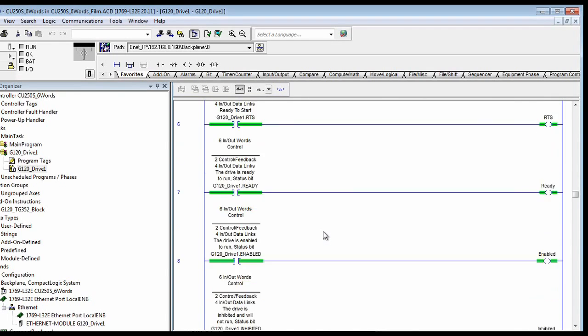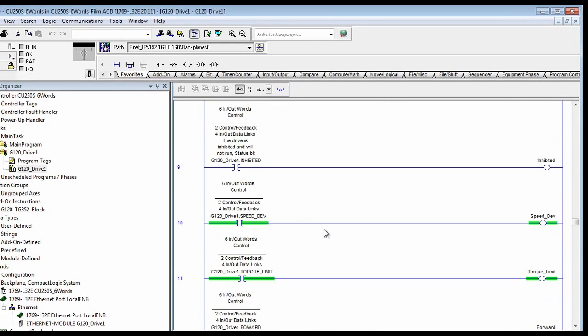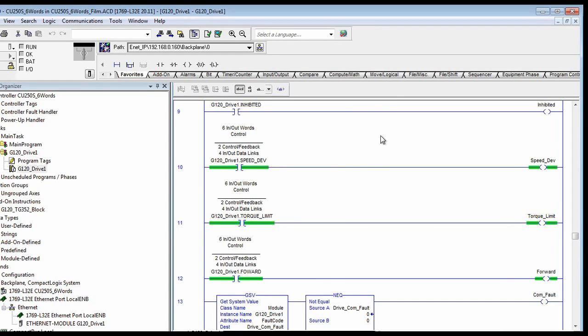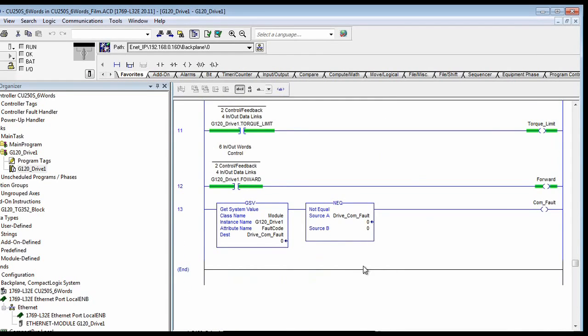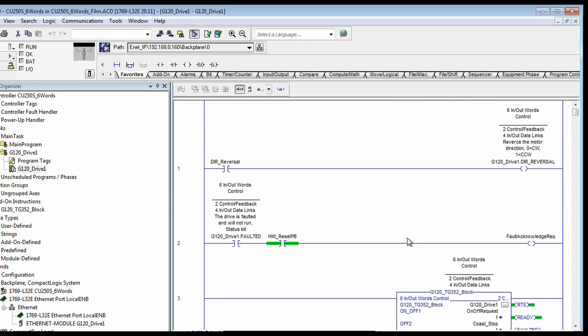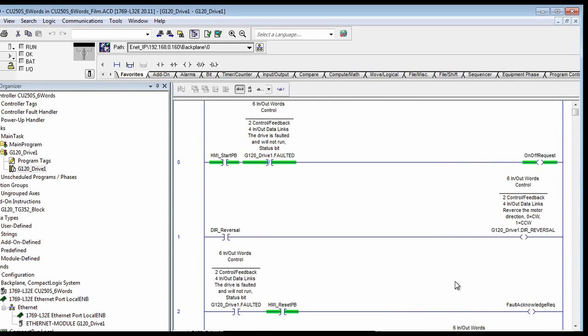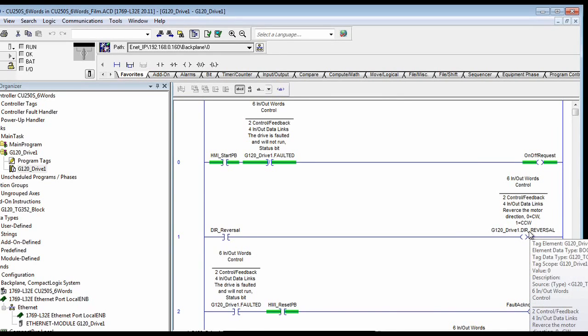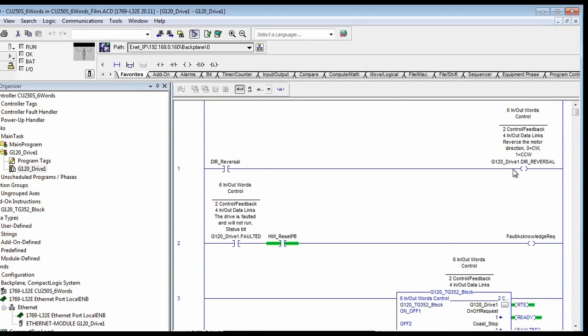As you can see, here are the other bits brought out for display. Don't forget to use the get system variables like you should do with any IO in an Allen Bradley to confirm that the module is actually online. Here I'm actually setting a few command bits. You can always get to bits that aren't exposed by the block by simply using the block name and then the bit name or the variable.